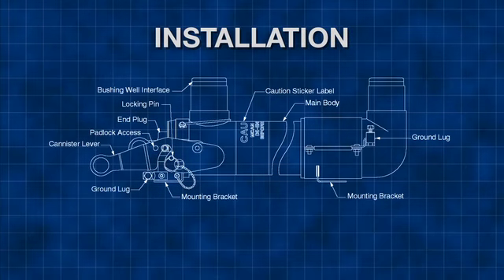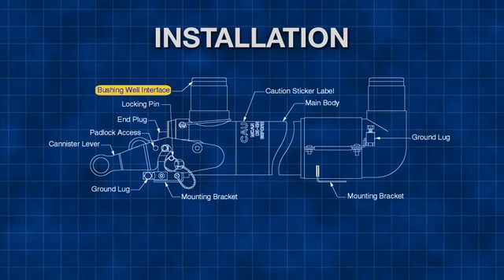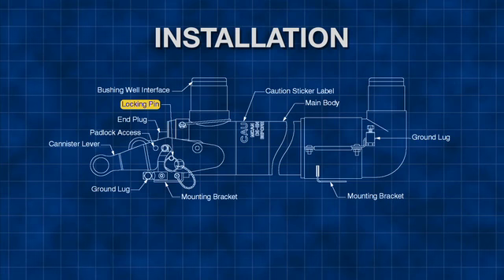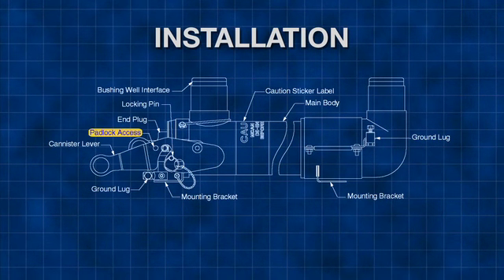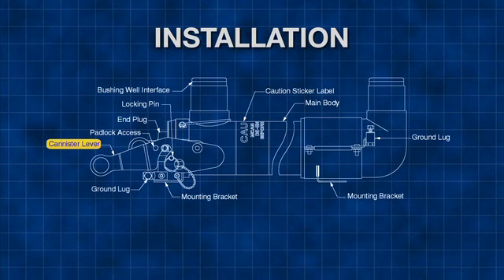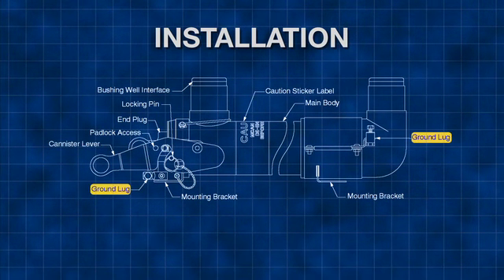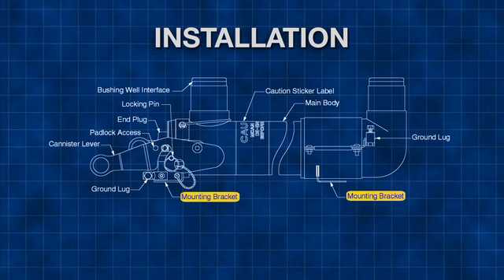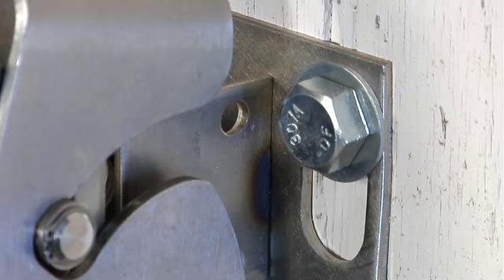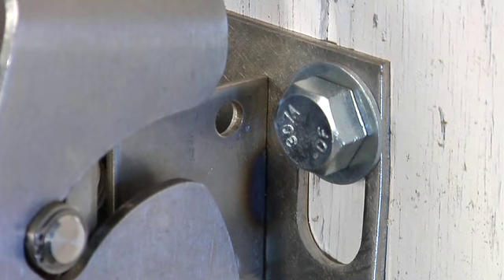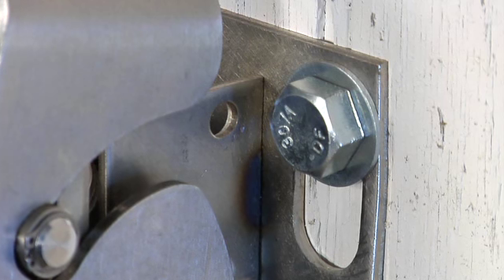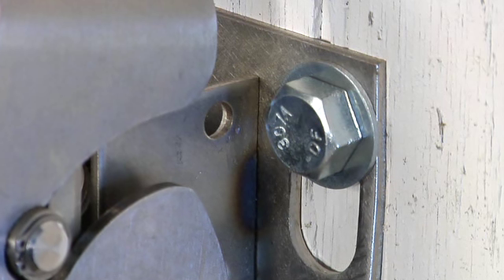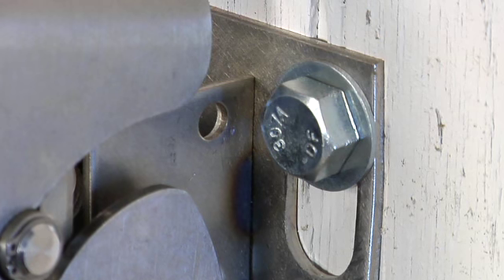Let's take a look at the various parts in a molded fuse canister. A molded fuse canister is made up of the main body with bushing or bushing well interface, the end fitting with bushing or bushing well interface, the locking pin, padlock provisions, the end plug, the canister lever, 2 ground lugs, and the mounting bracket or mounting feet. It is important when securing fuses that they are all secured by a bolt and washer at each mounting foot, located at the bottom of the unit. Be sure to use spacers if the wall is uneven.